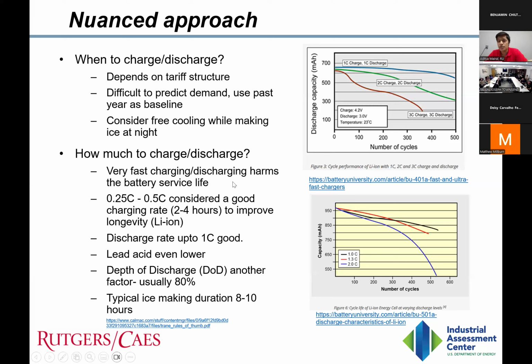And then how much to charge and discharge, this is again another thumb rule. The most common value you'll see in any modeling software is called a C value. It might be 0.5 C, 0.25 C. What does it mean? If I have a battery of 80 kilowatt hours, it means the battery provides 80 kilowatts for 1 hour. That is 1 C, just providing the rated power for 1 hour.